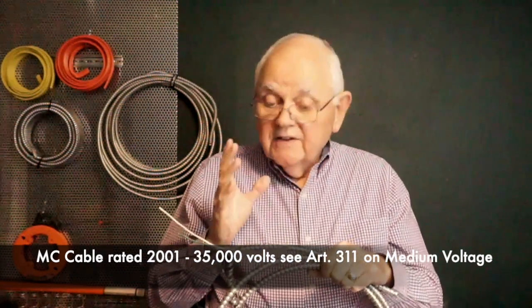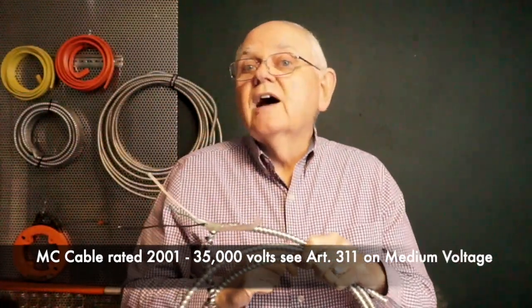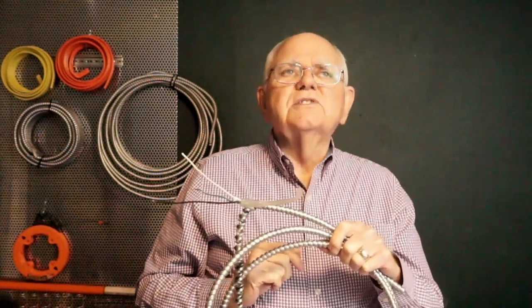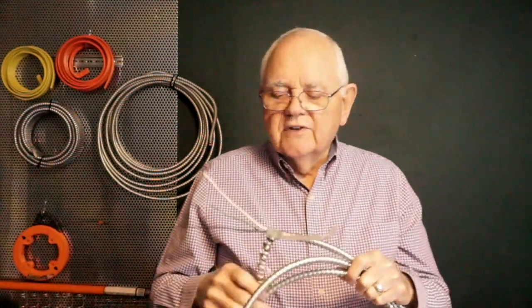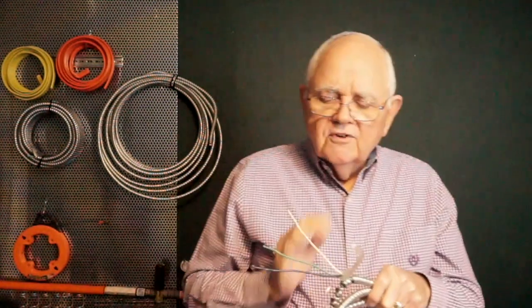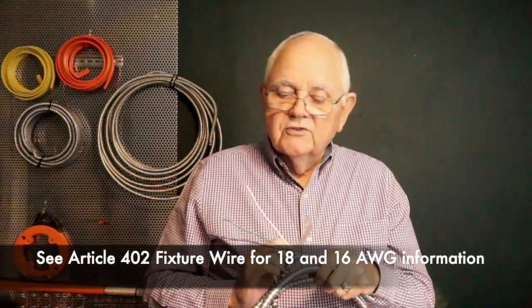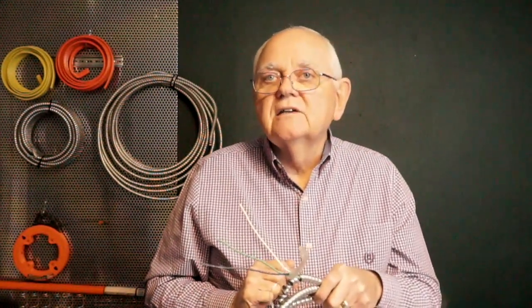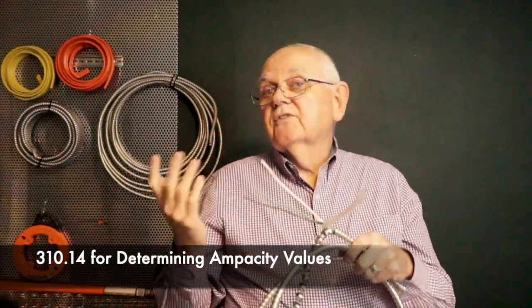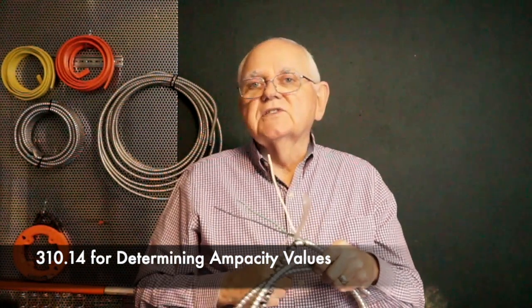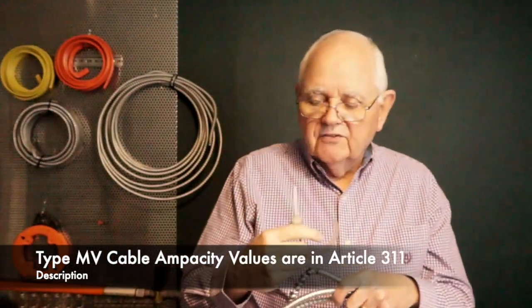So we use a lot of MC cable out in industrial facilities that's rated all the way up to 35,000 volts. However, we usually don't refer to it as MC cable. We probably just call it MV cable, okay, medium voltage cable. So anyway, for the 16 and 18, I have to go for the insulation types and the ampacity values. I'm going to end up back in my fixture wire article, Article 402, where Table 402.3 is going to cover the different types of insulation I can use at 16 and 18 AWG. For my 14 and larger copper or 12 and larger aluminum, I'll go to Article 310, specifically 310.14, in order to determine ampacity values for these conductors. And then for the medium voltage, the 2001 to 35,000 volts, once again, I have to go to Article 311 for ampacity ratings on my conductors.